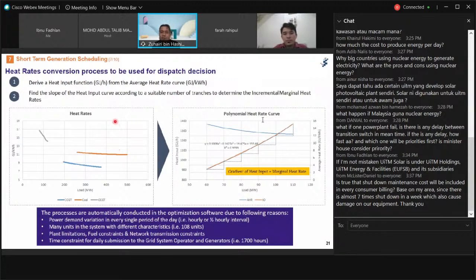What do we do with this heat rate? It gets converted into the heat input function, and from that function we find the slope of the curve according to a suitable number of tranches. The tranches simplify the slope, using what's called the piecewise linear method. We slice down the heat input curve to get the best estimation of the slope, and from that slope we can determine the incremental marginal heat rates, which are used for dispatch decisions for all the machines.